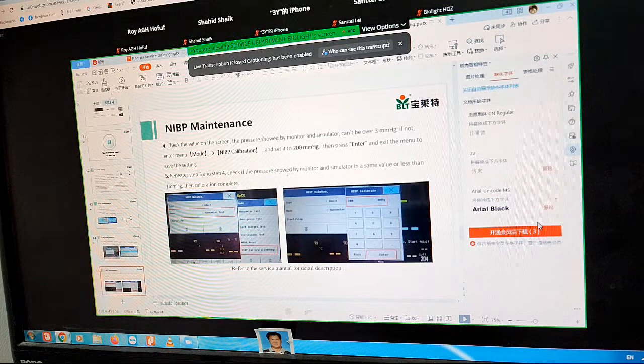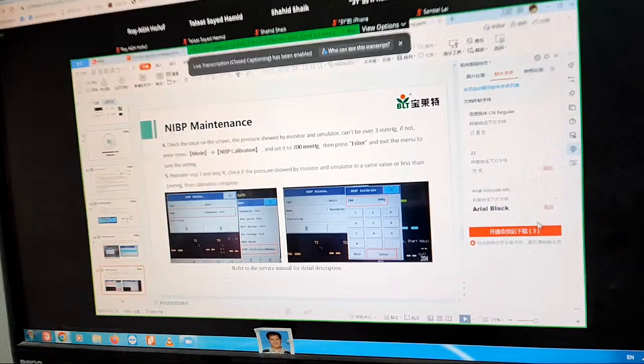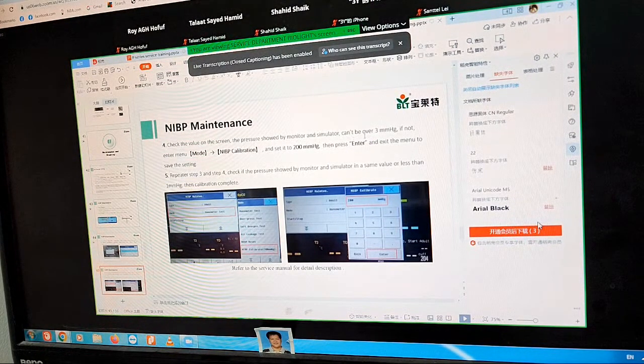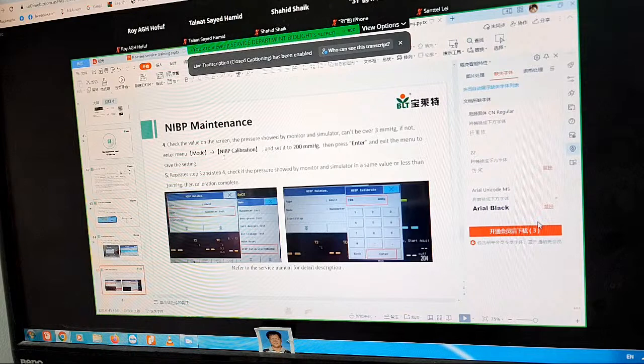So we make sure our NIBP calibration is correct. The tolerance still can't be over 3 millimeters of mercury, same as the P series and S series. We go to the NIBP calibration and set it to 200 millimeters of mercury, then press enter and exit the menu to save the setting.